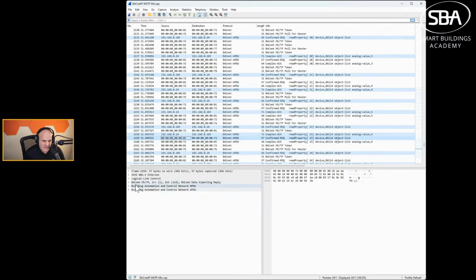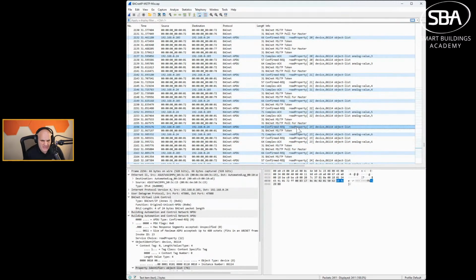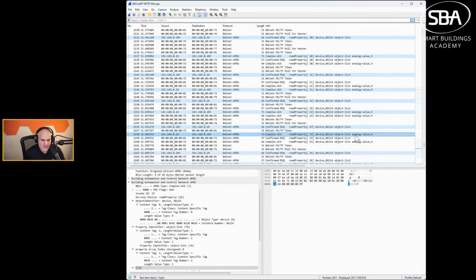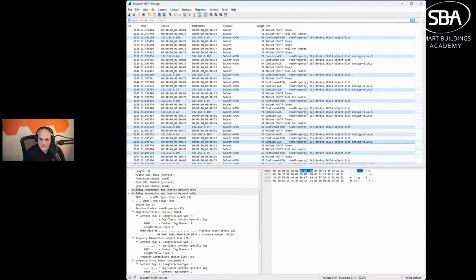And you'll see when I click on 86114, now I've switched over to MSTP, right? And so MSTP is going to go and message, and then it's going to be able to go and respond. So I'll get all that back. And so what will happen, right? I'll do my read property, and I'll get my acknowledgement. And in order for it to do that, I actually have to execute it on the BACnet MSTP side as well. So you'll see kind of how that works. Pretty interesting.